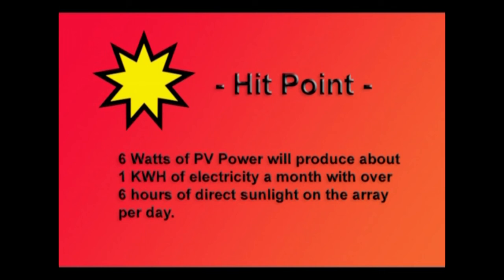Here's what I call a hit point, something you need to memorize. 6 watts of photovoltaic power from your array will produce about 1 kilowatt hour of electricity per month with over 6 hours of direct sunlight a day on the array. So that means after you get about 6 hours, 7, 8, you might do a little better than this. But with an average of about 6 hours, maybe a little more, you're going to start to really accumulate about 1 kilowatt hour of electricity a month for every 6 watts that your photovoltaic array puts out.